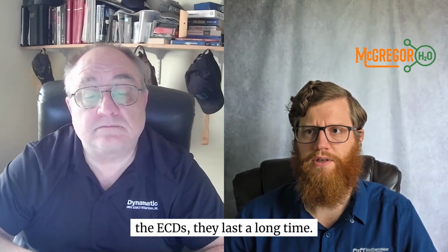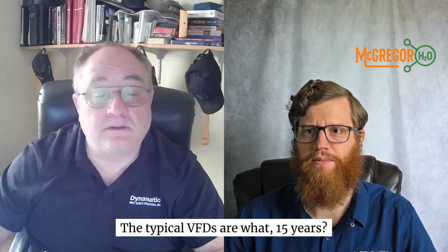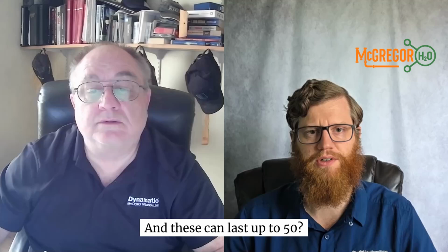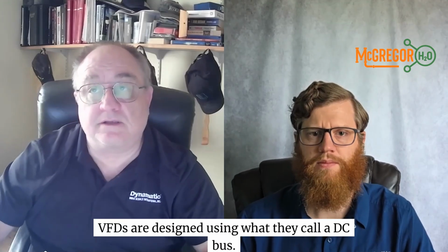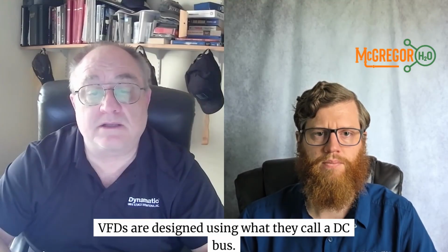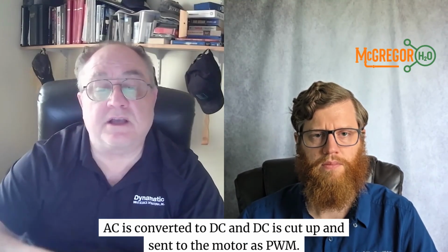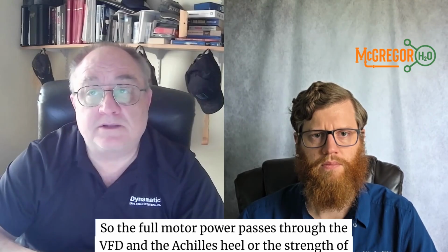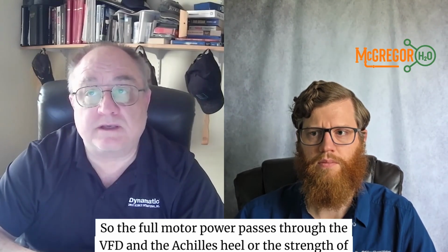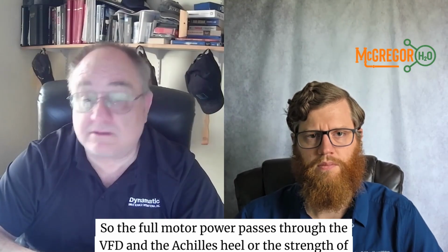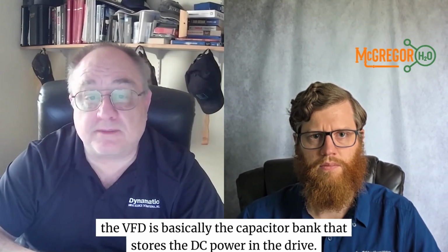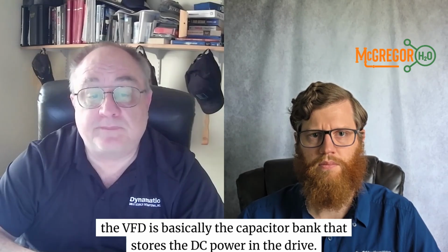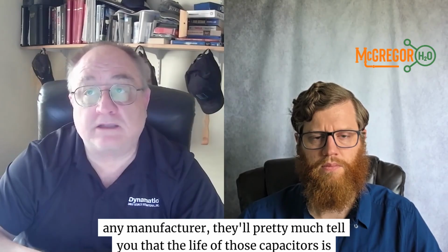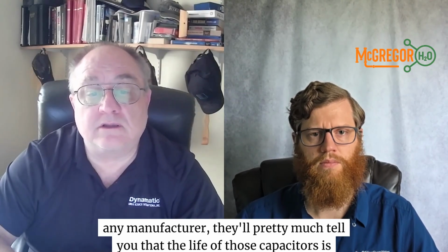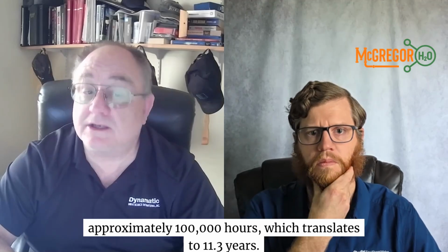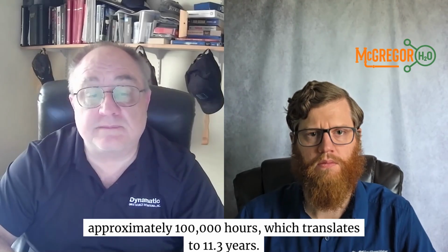Right, yeah, exactly. So the ECDs, they last a long time. The typical VFDs are what, 15 years, and these could last up to 50? VFDs are designed using what they call a DC bus. AC is converted to DC, and DC is cut up and sent to the motor as PWM. So the full motor power passes through the VFD, and the Achilles heel or the strength of the VFD is basically the capacitor bank that stores the DC power in the drive. And if you pick up most manuals from any manufacturer, they'll pretty much tell you that the life of those capacitors is approximately 100,000 hours, which translates to 11.3 years.